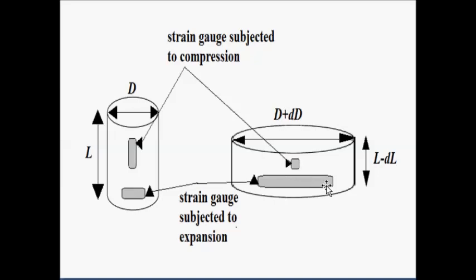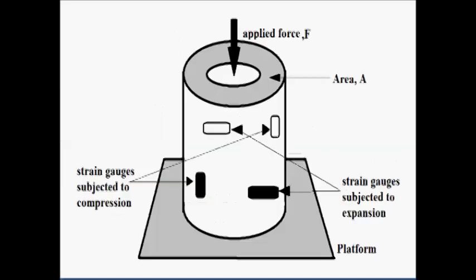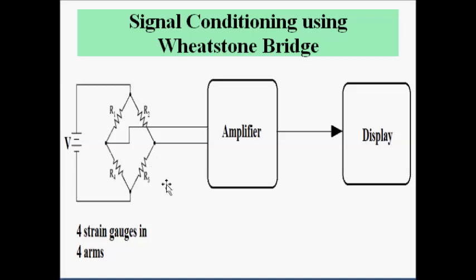The axial and circumferential strains can be converted into a suitable current or voltage signal with the help of a Wheatstone bridge. There are four strain gauges in total, forming the four arms of the Wheatstone bridge. The output is taken across the opposite end to the pair of ends across which the DC supply is connected. It is then amplified and given to a display unit. The four resistances in the bridge actually represent the four strain gauges.